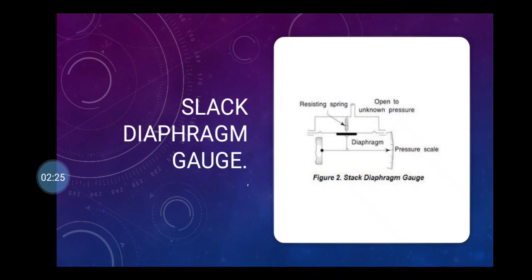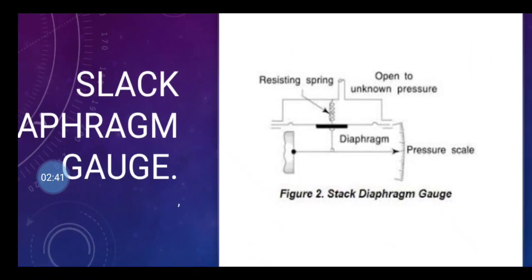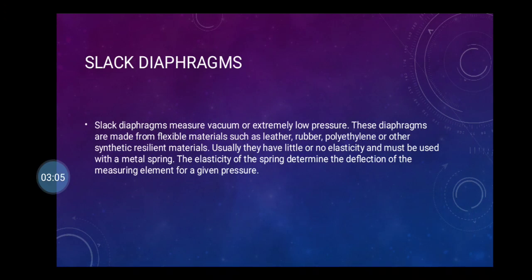the slack diaphragm gauge. The slack diaphragm gauge consists of a pivot, pointer, scale, diaphragm, unknown pressure and resisting spring. This figure shows the slack diaphragm gauge. With some modification in the diaphragm, even pressure below atmospheric pressure can be measured by the slack diaphragm gauge. For a small change in pressure, the diaphragm is able to produce a large change in the force. Instead of a tight diaphragm, it is slack. It is allowed to move a large distance in response to a small change in the pressure.